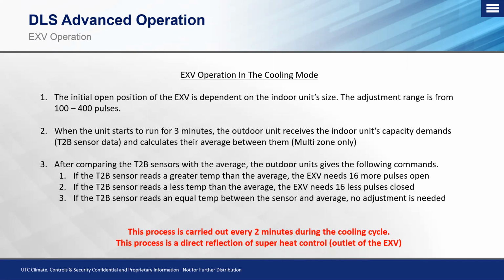It's like a sweet spot, like we talked about for the compressor. It's almost like a sweet spot for the EXV. Okay, it's going to maintain that minimum position and open and close as needed, depending on what the indoor unit running conditions and demands are. Because that capacity demand changes as we get closer to load and as we get further away from load. But that T2B sensor is one of the factors that controls that sweet spot of those EXVs are maintaining their minimum positions across there. Okay.